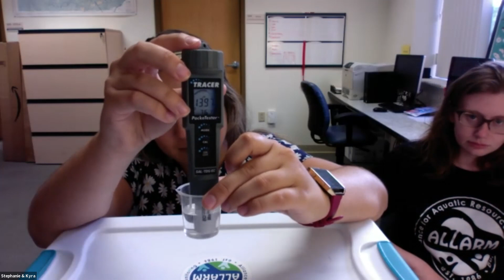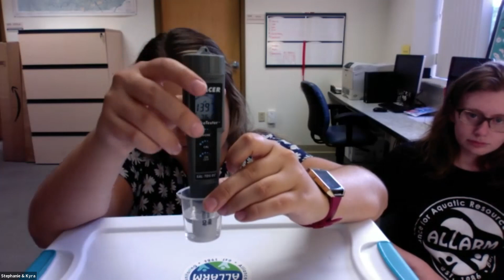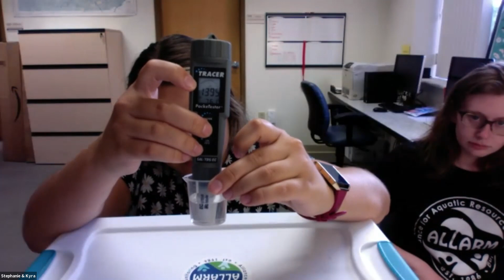And Stephanie, you're fluctuating between 1396 and 1397, so I think that is stable enough. So we're going to go ahead and go through that calibration process again. So watching this here, the meter is stable. We're going to press and hold the cal button for approximately 2 seconds until cal appears on the bottom of the screen, and 1413 begins to flash. Look, yeah, you can release.